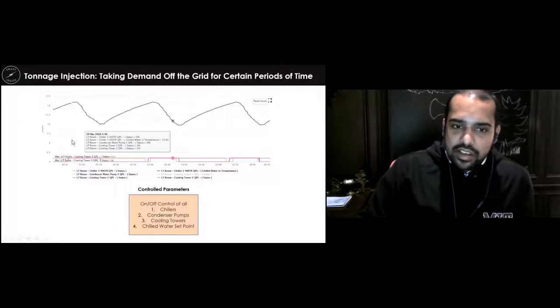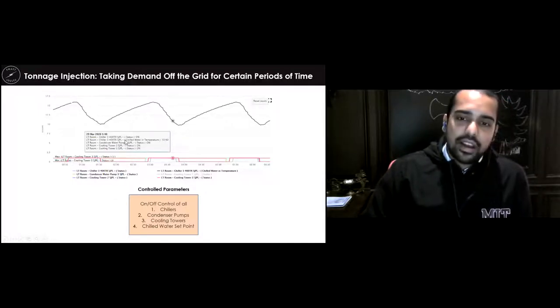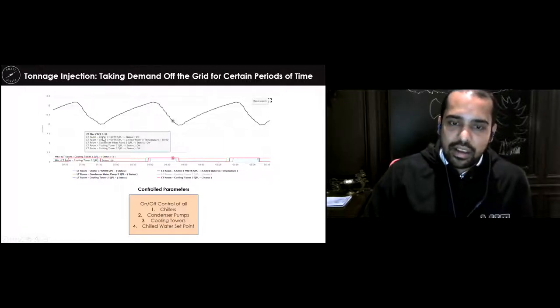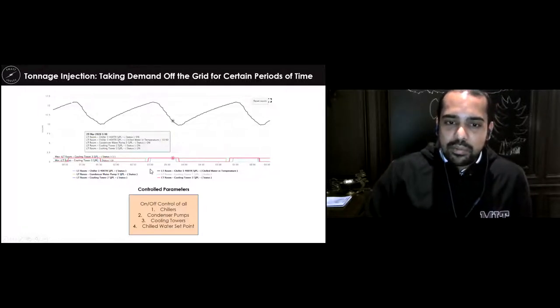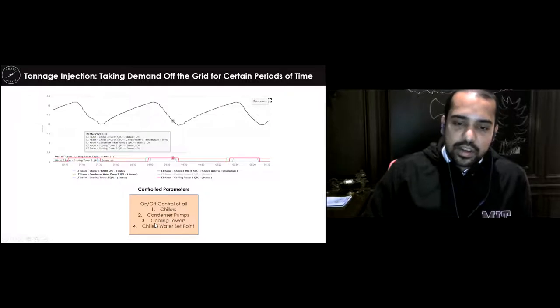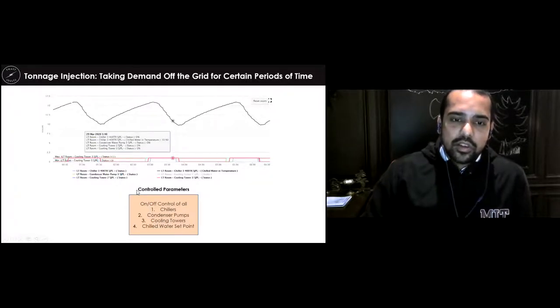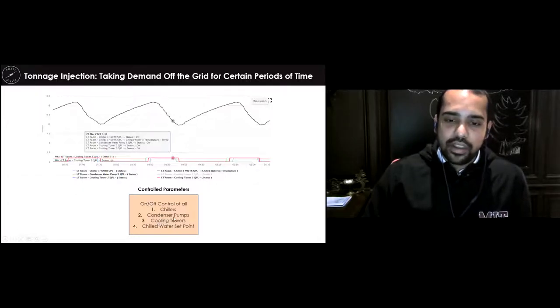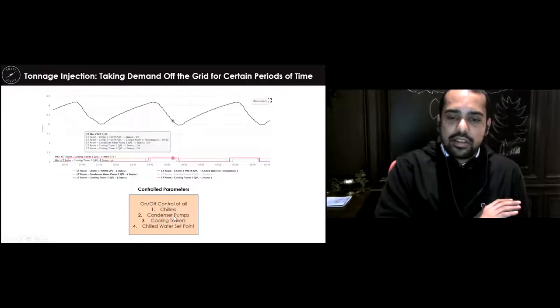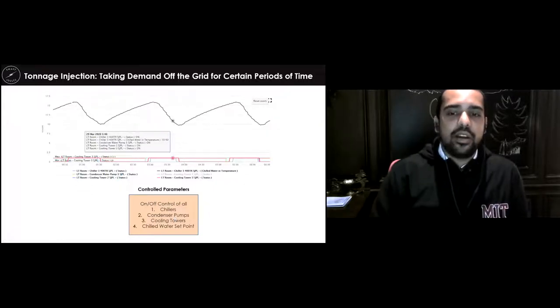And what does tonnage injection mean? This means that you actually overcool the building for a little bit. You reduce the chill water set point to the minimum, you overcool the building, and then you shut the entire chillers, condenser pumps, and cooling towers off. So you just take the largest load in the building off.